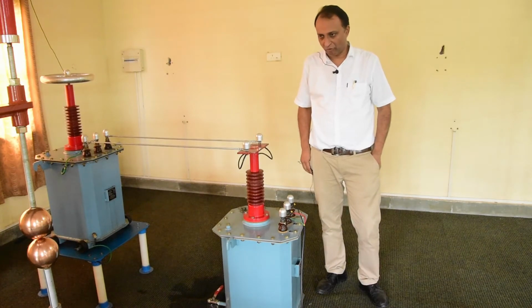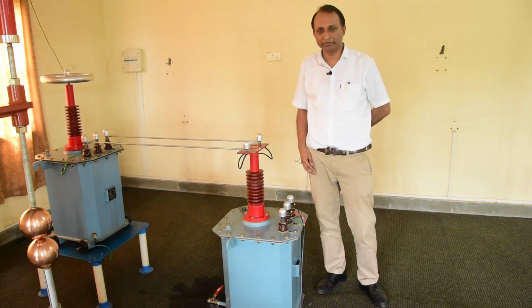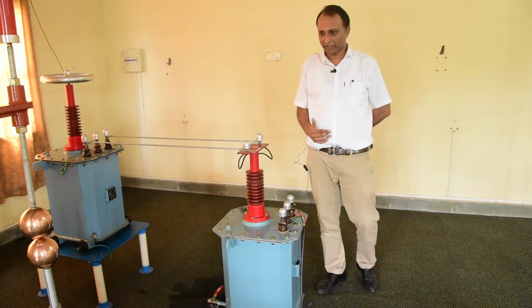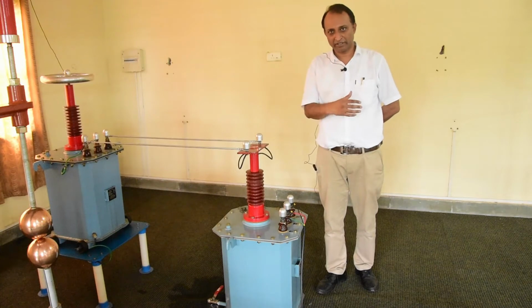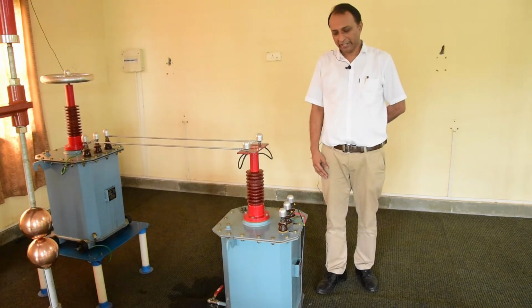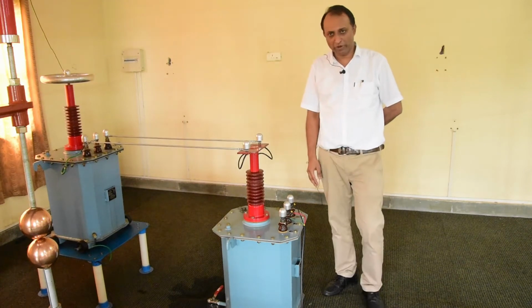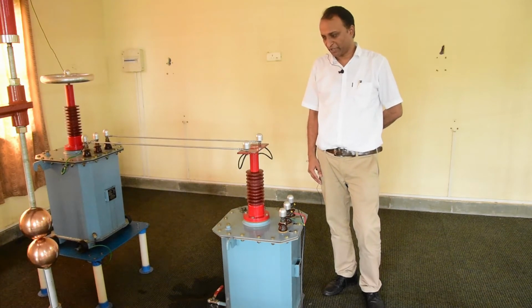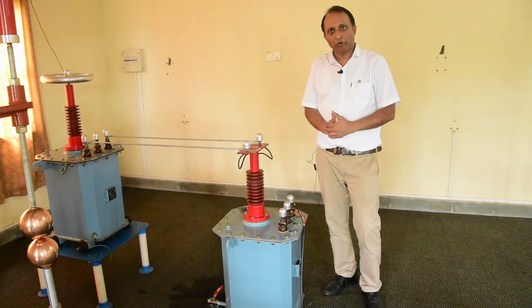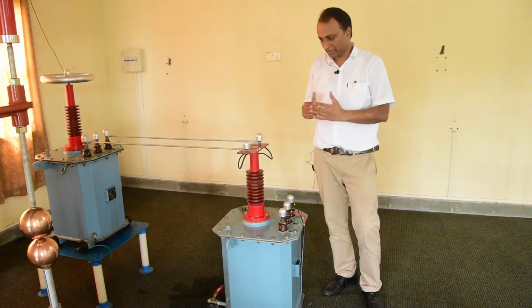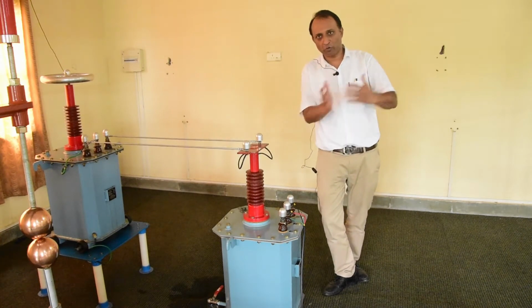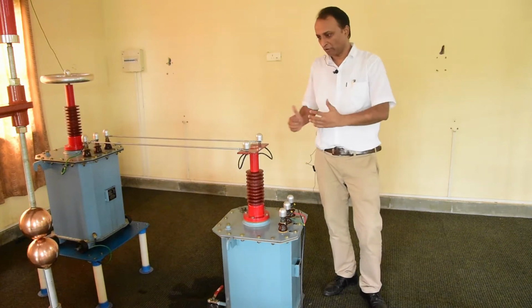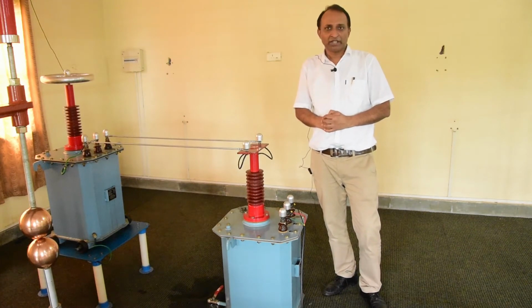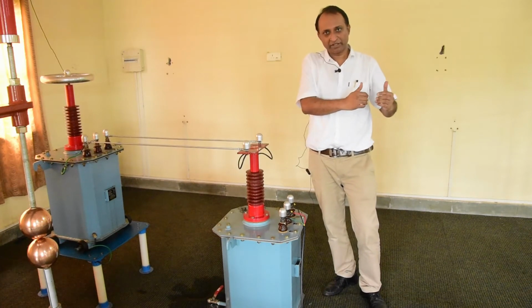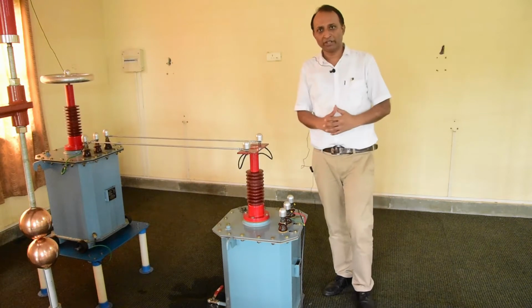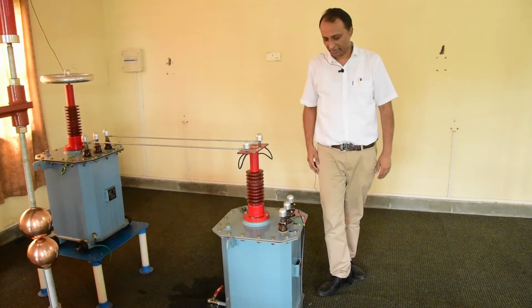cage meant for installation of sphere gap assembly, and I have ensured that all the components of this assembly are de-energized, and so also they have been grounded properly from any presence of any static charges. So while we perform the experiments on sphere gap and this high voltage assembly, we are supposed to stand outside the cage, ensuring that all the safety norms are followed, and then remotely the operation is controlled from the control panel. So the control panel is outside the cage.